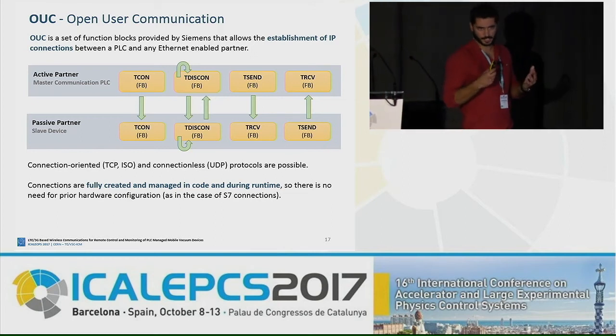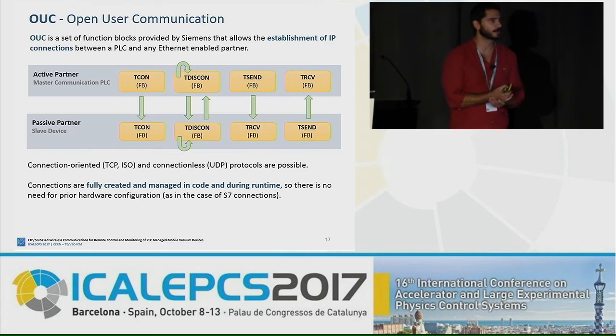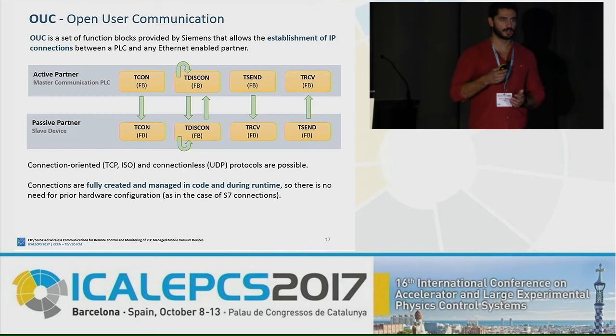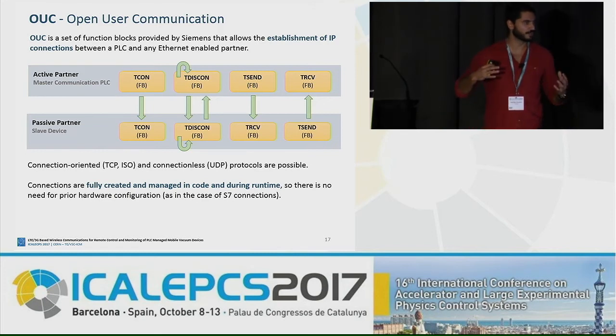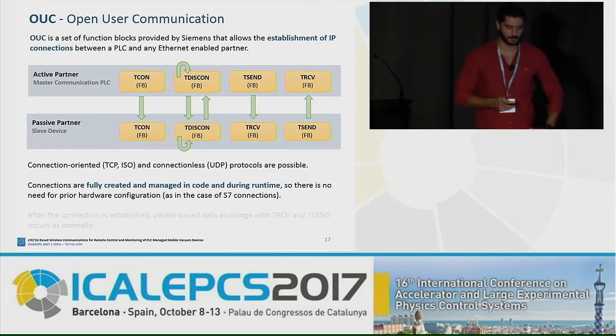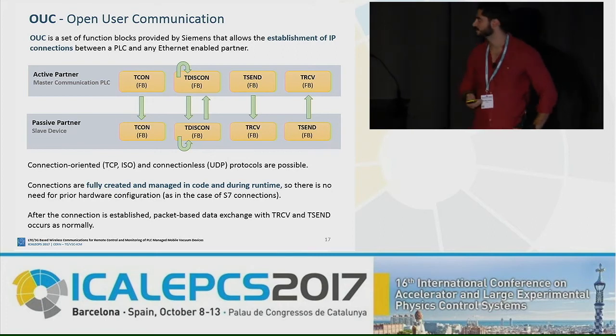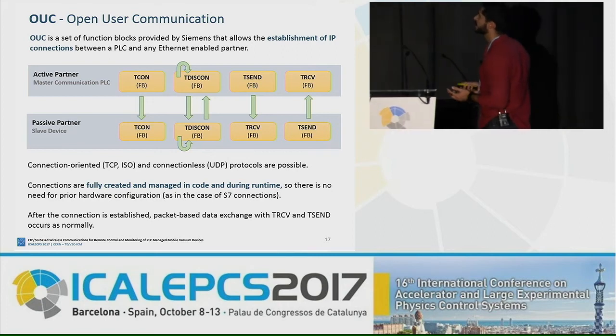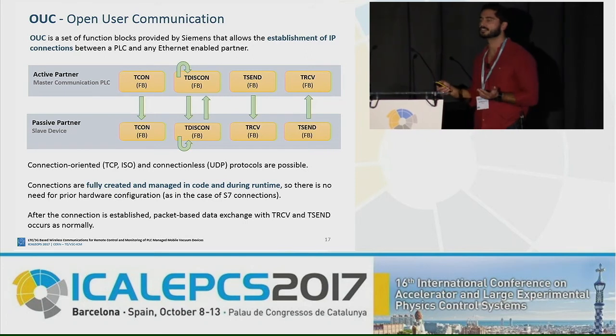So with this, it's much better because every time we add a new SIM card or a new mobile device which needs to be connected, we simply do it in code. So we don't need to reprogram anything. We just add a new block with this IP, which is really a blessing for our case. Usual stuff: connect, disconnect blocks. You send and you receive data with T-receive and T-send blocks.